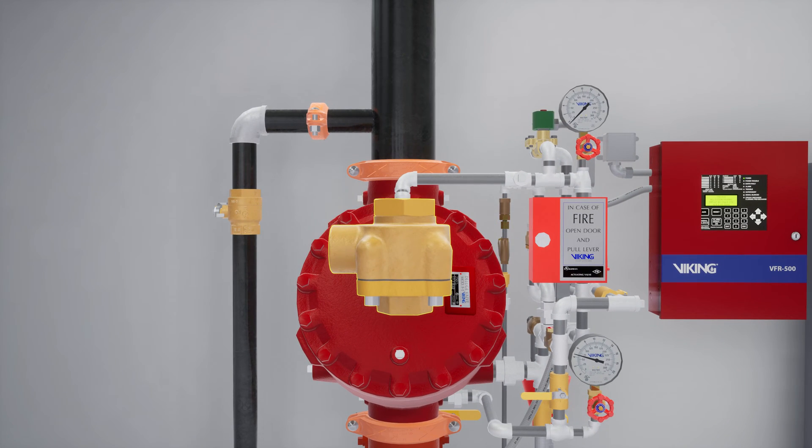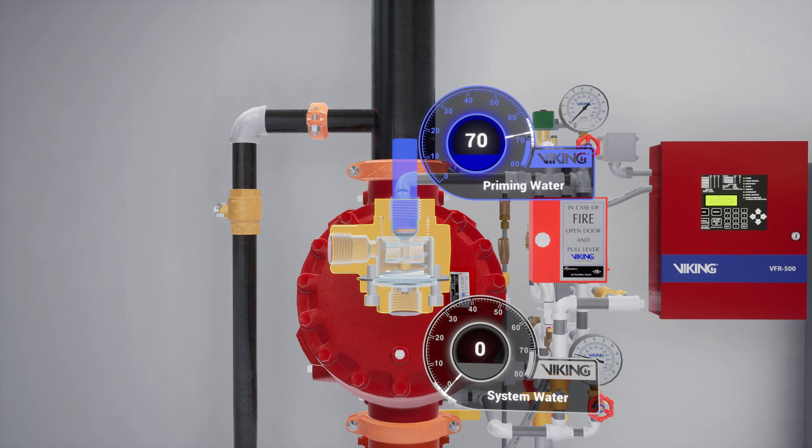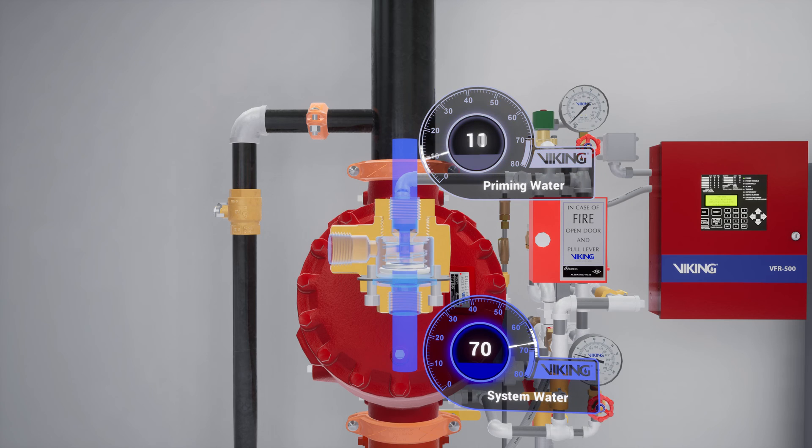Following the trim off the prime chamber is the Pressure Operated Relief Valve, or PORV. The PORV is a device that ensures the valve remains in an open state while water is flowing through the valve. When water is directed to the sensing side of the PORV, the push rod is forced open. Priming water is then directed to the open drain, preventing the priming chamber from repressurizing.